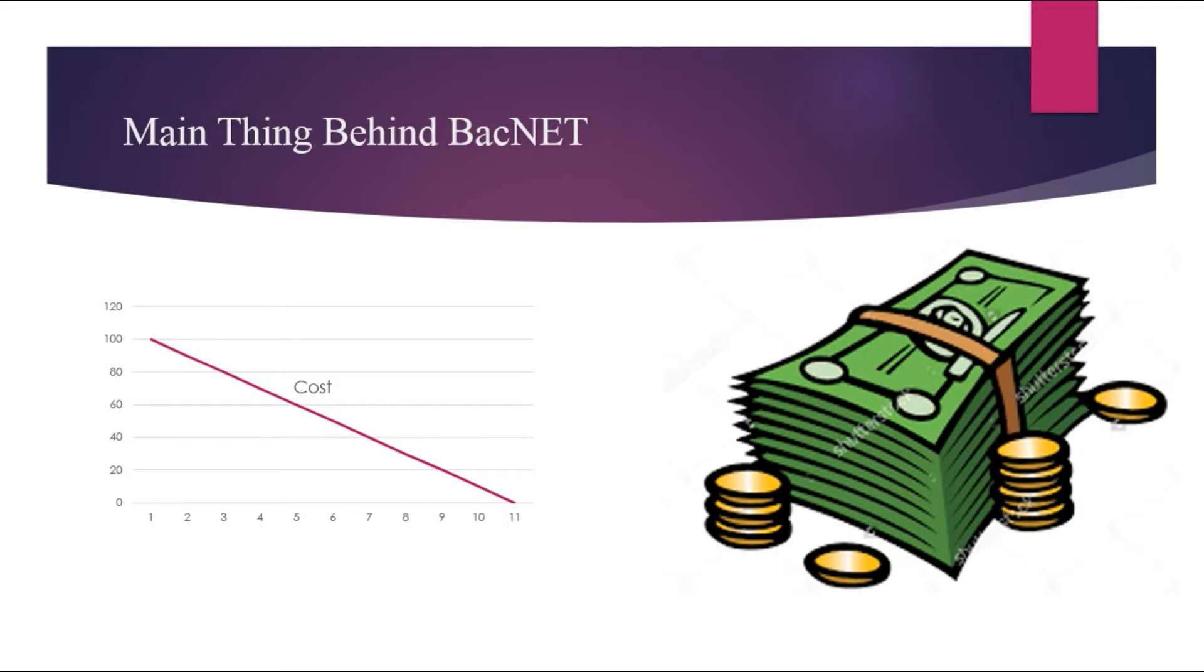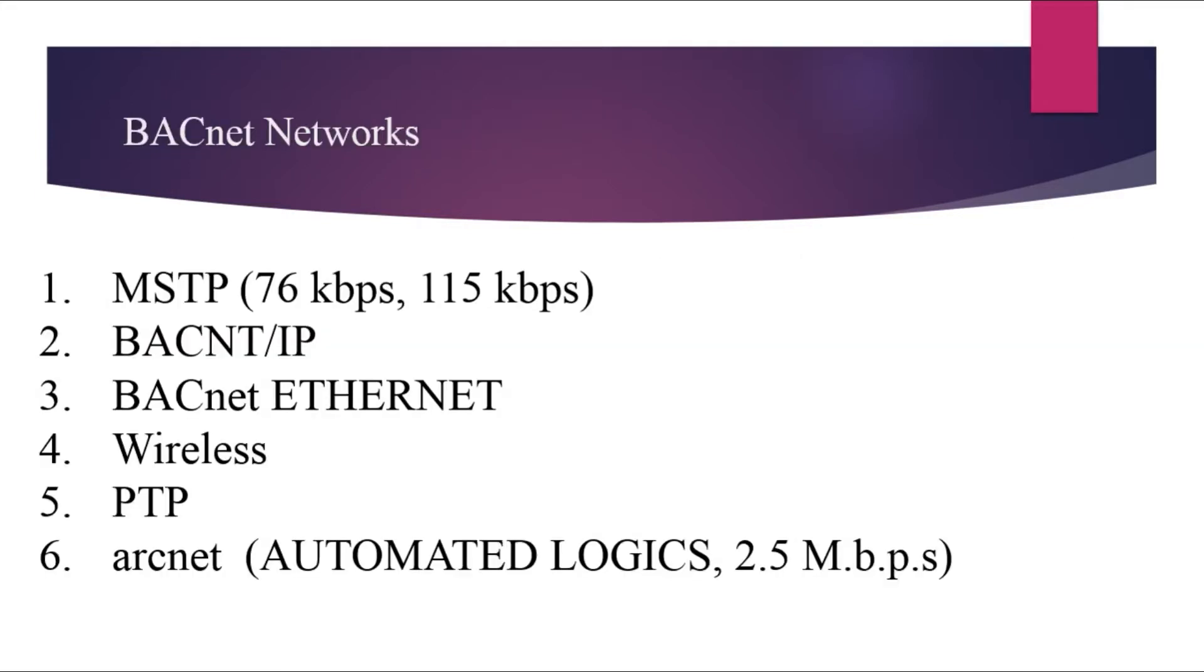BACnet protocol can be defined on the basis of different communication media like MSTP which is master-slave token passing, then BACnet IP and then BACnet Ethernet and so on. So in this video, we will perform the basic read property operation for analog and digital input over the BACnet IP.